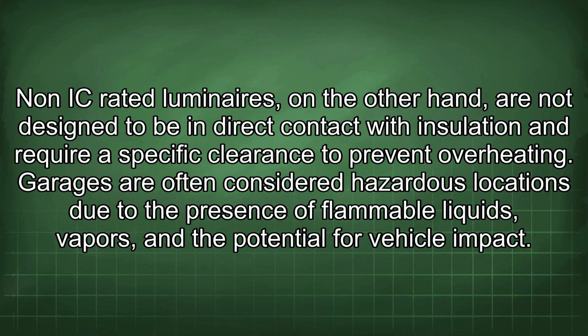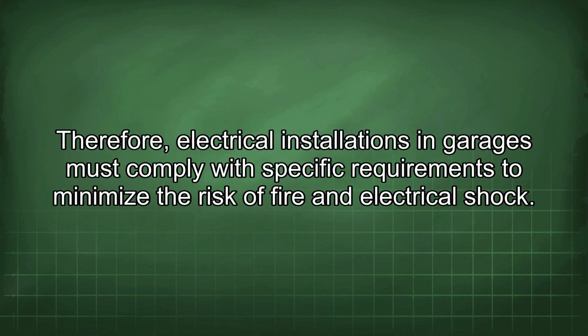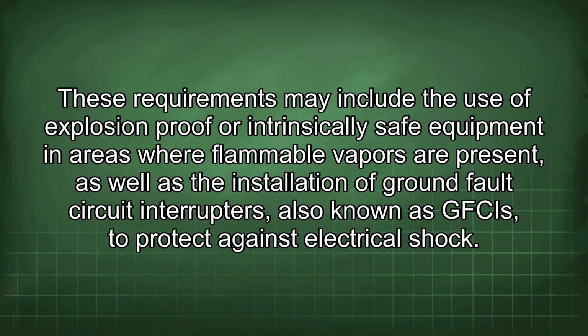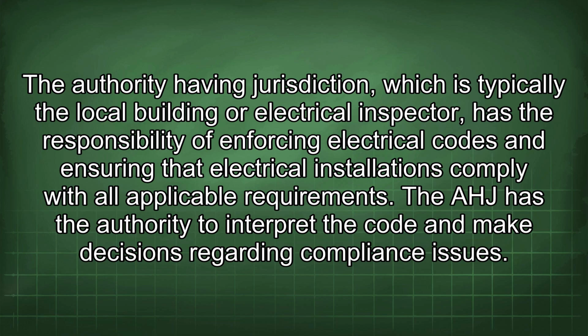Garages are often considered hazardous locations due to the presence of flammable liquids, vapors, and the potential for vehicle impact. Therefore, electrical installations in garages must comply with specific requirements to minimize the risk of fire and electrical shock. These requirements may include the use of explosion-proof or intrinsically safe equipment in areas where flammable vapors are present, as well as the installation of ground fault circuit interrupters, also known as GFCIs, to protect against electrical shock. The authority having jurisdiction, which is typically the local building or electrical inspector, has the responsibility of enforcing electrical codes and ensuring that electrical installations comply with all applicable requirements.